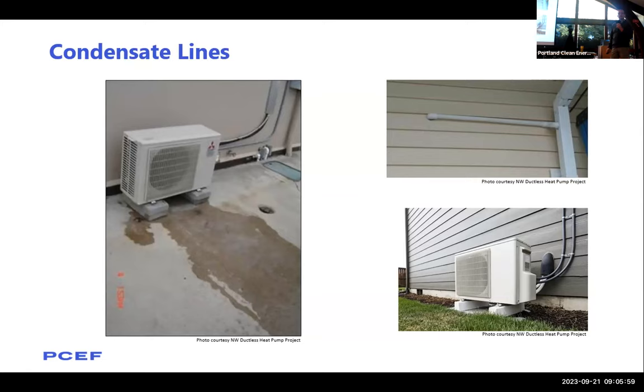I quite literally did that one time. We had the downspout plug up to the water level, and the downspout came above the condensation line, flew back into the unit and ruined the sheetrock. Oh, interesting. Okay. Yeah, downspout, don't do it. Okay. Good to know.